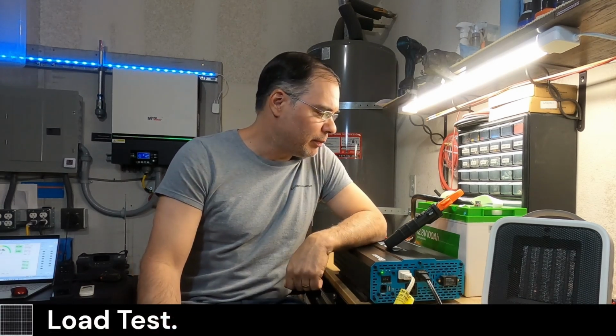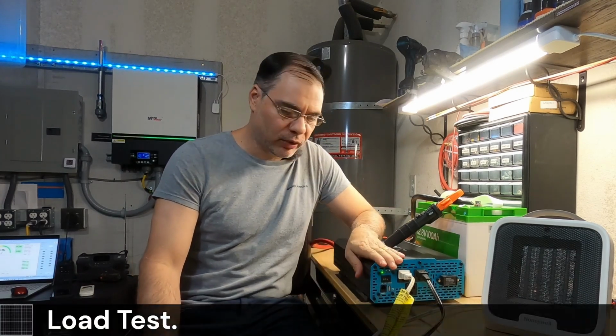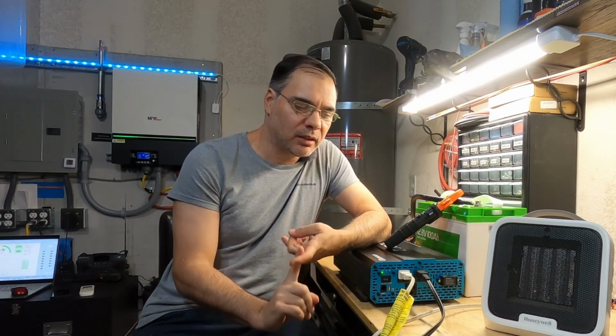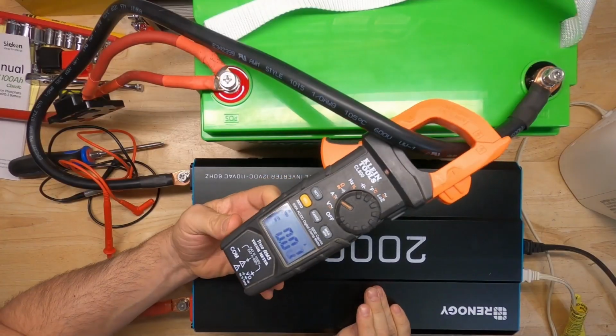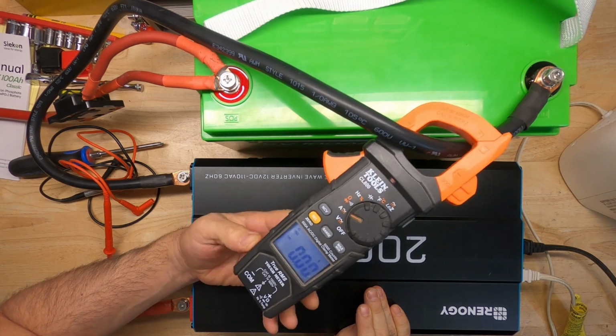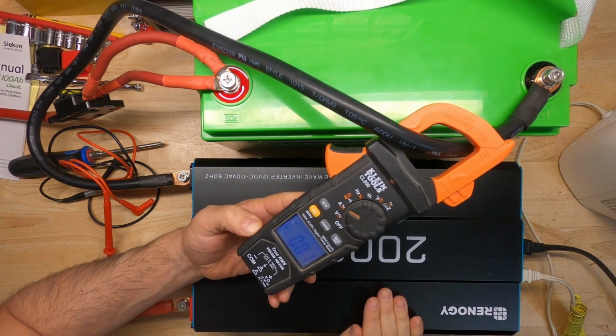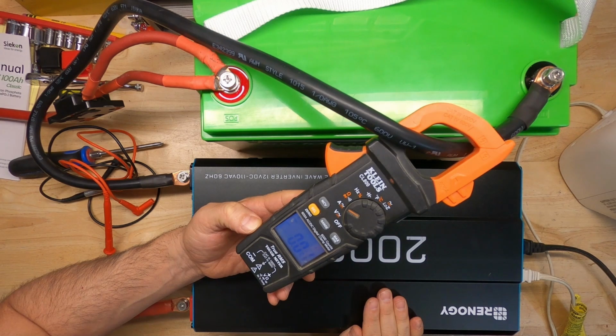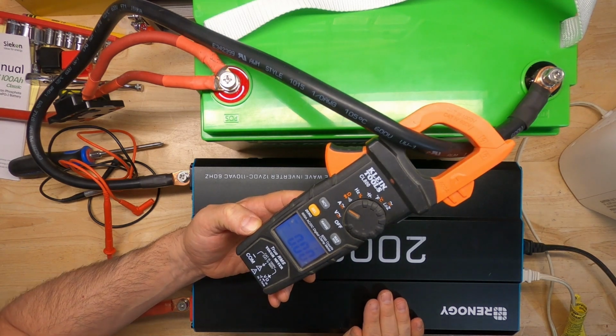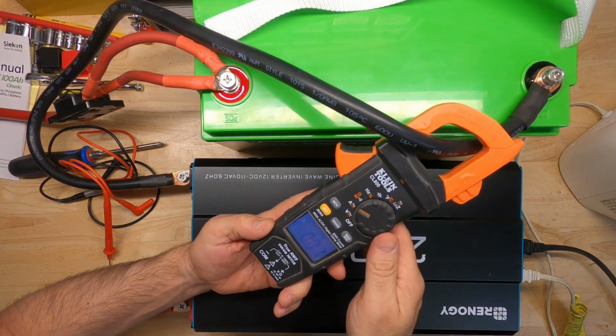Okay, the next test we're going to do are load tests. So we have the battery connected up to this 2000 watt inverter, and we have a couple of space heaters connected to the inverter. So we're going to test it at 200 amps or greater, and then we're going to test it at 150 amps, which is the rated surge capacity. Alright, so the first test will be a 200 amp test. Let's turn on the first space heater. What we should see is a complete disconnect, so it shouldn't be able to hold this very long.